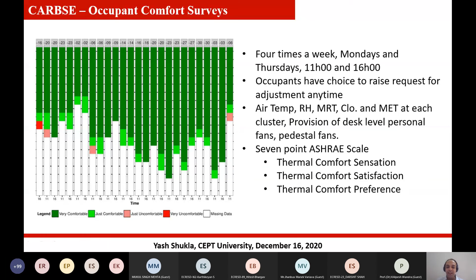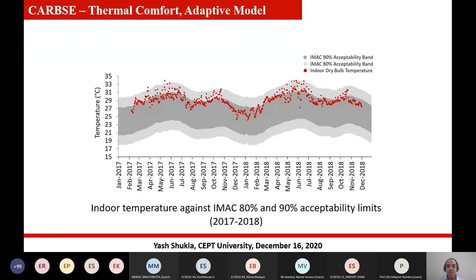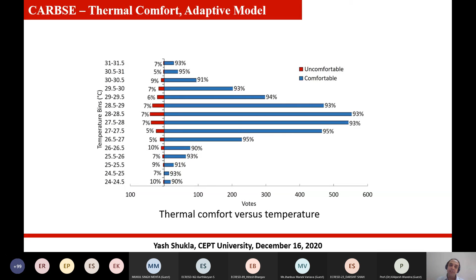And this is where we compared the band that I talked about at the beginning of the presentation, what my temperature conditions are, and these are the actual measured temperatures, and it's right close to the 90% band of the temperature we could maintain. So that showed that our building could achieve the temperature that we were planning to achieve. And at that temperature, 90 to 95% of people said that they are comfortable, even at the higher temperature. So once you reduce the wall temperature and window temperature, you can maintain a slightly warmer temperature. This was validated by the survey results together with the measurement data.